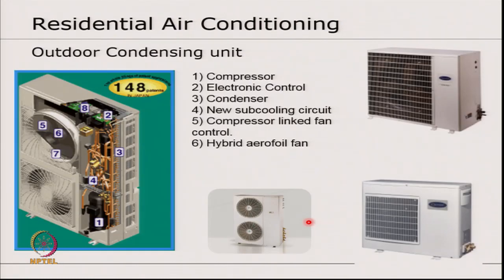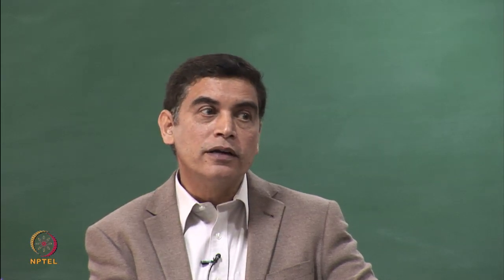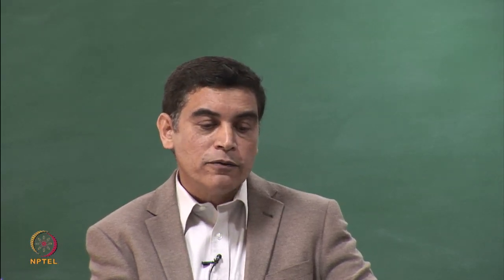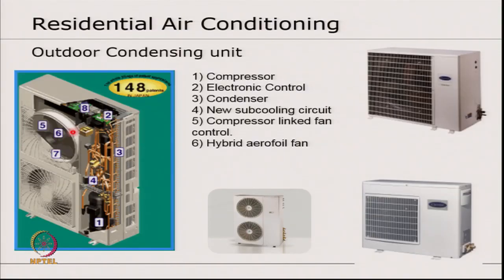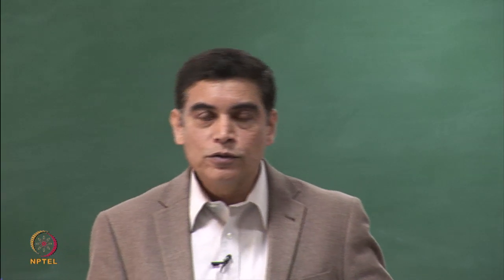Then I have another picture of the condensing unit where we can see it from another side, and here we can look at the fan, and the condenser fan is normally a propeller fan. So we would look for a fan which is different from what is used on the evaporator side. On the evaporator side we are addressing a heat exchanger which has both simultaneous heat and mass transfer. So there is high resistance there. Then there is an air filter, we need to compensate for that. So we end up using a forward curved blower in most cases, or a tangential blower in duct free splits. In condensers we would use propeller fans, generally made of plastic with a motor, and in some of the more advanced designs they would be driven by a DC motor. Again, the ability to modulate the airflow so that we can address varying ambient conditions, outdoor air conditions.